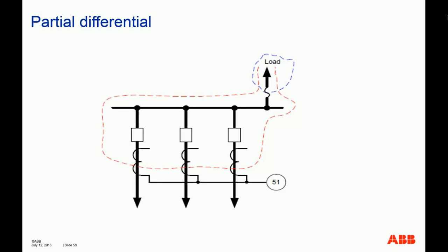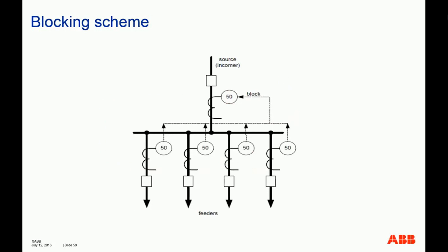So when you need to coordinate the overcurrent protection between the sources and the fuse, for example, or any feeder overcurrent relays downstream, you don't need to coordinate or draw 3 times the curve, because right now, since you sum them externally together, it only becomes one relay. So that actually reduces the amount of work and makes it easier. Okay. So next, blocking scheme.